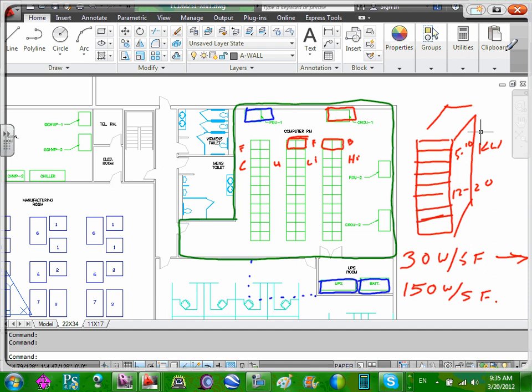But folks in the IT group who are very sophisticated, they can give me a list of the racks, if they know what they're doing, and some do. They're going to give me this whole row thing, and they're going to suggest that when they fill this rack up, it's 8 kW. And then this one is 6, 6, 6, 6, and I got a bunch of 8s. So then we can go through and really build the capacity of that data center. And what they give me might only be these two rows, and that's future growth. So we'll kind of average this or say, well, what's your future going to be?